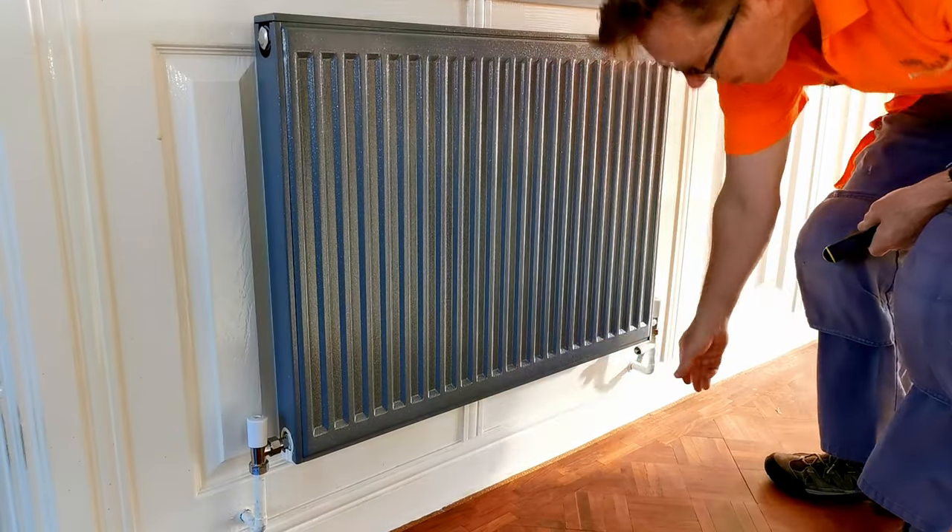The answer is to replace your old standard thermostatic radiator valves with auto balancing thermostatic radiator valves. Here are Drayton's auto balancing thermostatic radiator valves - a brand new product released August 2022. With these, you leave the lock shield fully open and do all the balancing on the thermostatic radiator valve. When a thermostat turns off, these auto balancing valves recognize that the pressure has increased and restrict the flow to keep it the same through the radiator. So although the pump stays pumping exactly the same, these new valves maintain the flow, keeping your 11 degree drop through the radiator and maintaining the return temperature to the boiler, keeping it working at its most efficient.